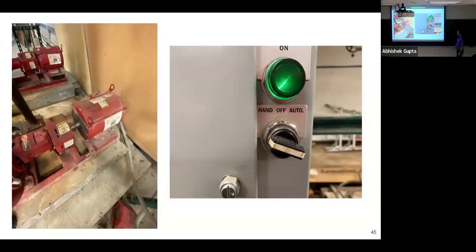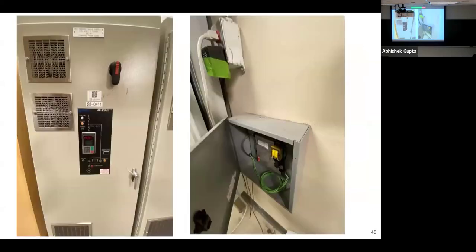This picture shows a hand-off-auto switch. Right now this piece of equipment is running in hand. If it were in auto, the control system would be sending the signal to turn it on or off. This equipment is overridden because it's switched to hand. We don't know why — maybe they were working on something or had to modify something in the building — but this is something we'd call out in an assessment to the building control system team.